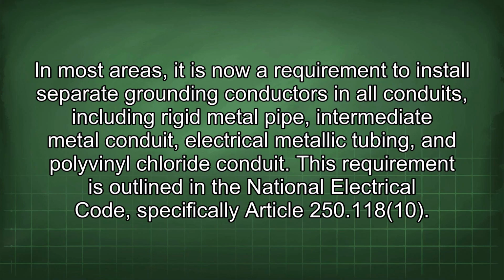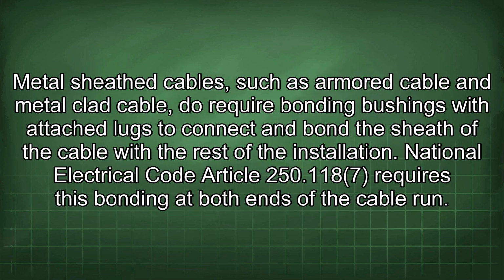In most areas, it is now a requirement to install separate grounding conductors in all conduits, including rigid metal pipe, intermediate metal conduit, electrical metallic tubing, and polyvinyl chloride conduit. This requirement is outlined in the National Electrical Code, specifically Article 250.118. Metal sheath cables, such as armored cable and metal clad cable, do require bonding bushings with attached lugs to connect and bond the sheath of the cable with the rest of the installation.